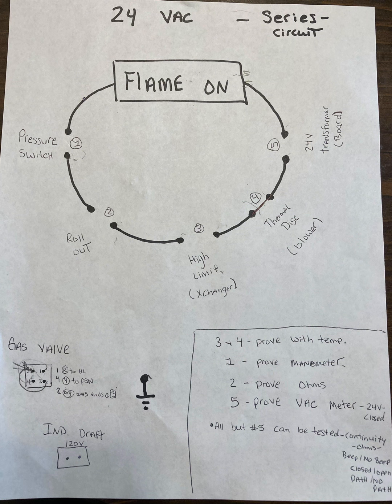It also is temperature, and it also is individually based, so it says it right on it. At what temperature do I open, and at what temperature do I close? This can be tested with your hopscotching method with the unit on. You can have 24 volts coming to it. You don't have it coming out of it.